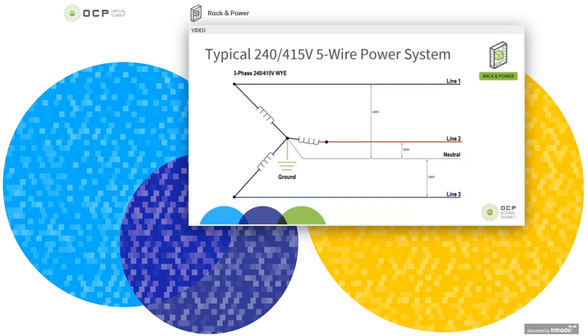Each power feed out of these systems at the IT load is still single phase, but they come into the rack or into the cabinet as three phase power. So you typically see a three leg system, line one, line two, and line three, and a neutral in these systems, and always a safety ground. So the single phase power is sourced from the line to the neutral, from the line to the neutral, line to the neutral, to get the three single phase feeds. This is very typical in Europe. It's gaining a lot more adoption in the United States now, first by the large enterprise users like Microsoft. And now you see it filtering down into a lot more of the new builds because it saves on copper and electrical infrastructure to use the higher voltage system.